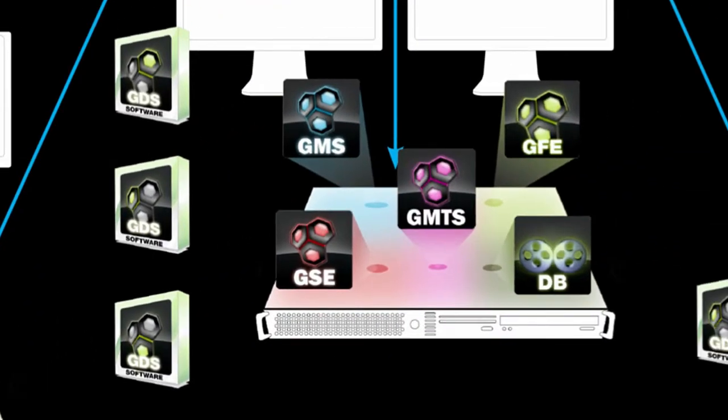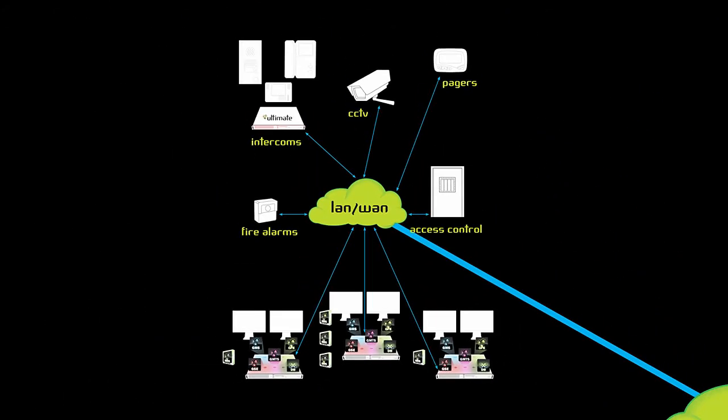What makes Genesys truly unique is that individual driver instances are set up for each system connected within the Genesys driver service. Driver separation allows for the load of all the drivers running to be spread across the system, enabling large numbers of drivers to be connected. The GDS monitors each driver instance. If they become unstable or fail due to poor third-party software such as SDKs, the GDS can close down the individual driver to ensure it doesn't cause a problem to any other part of the system, at the same time as generating an alarm event.